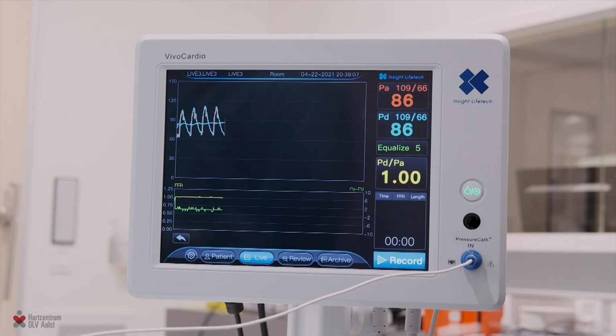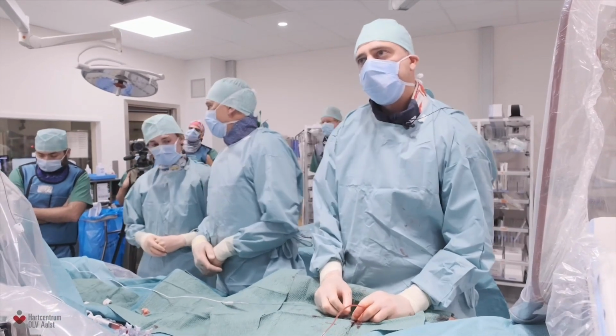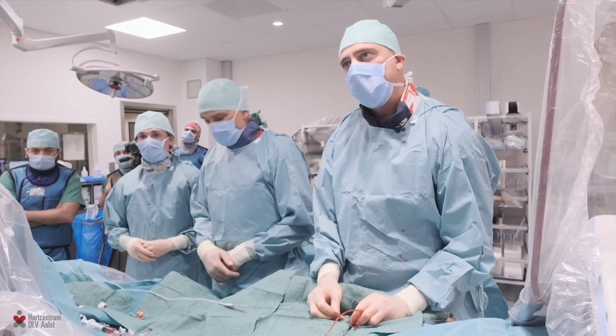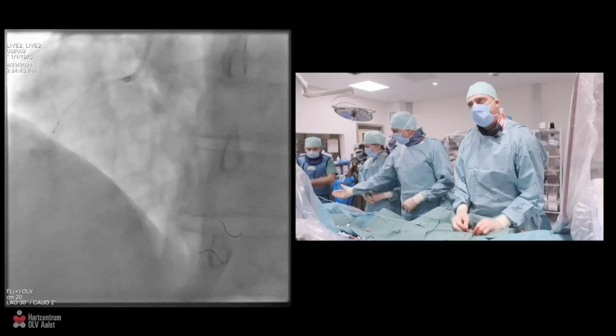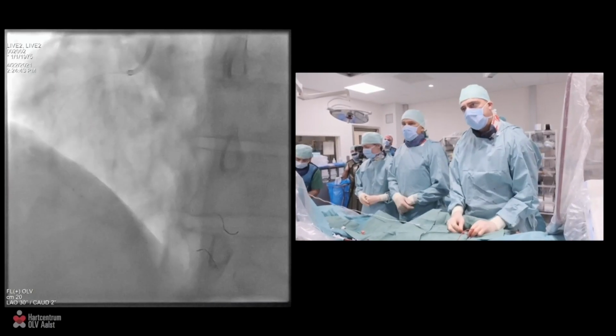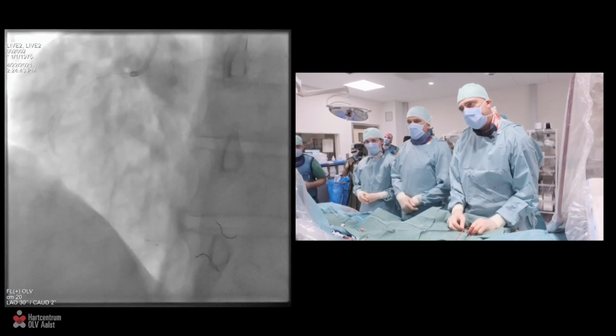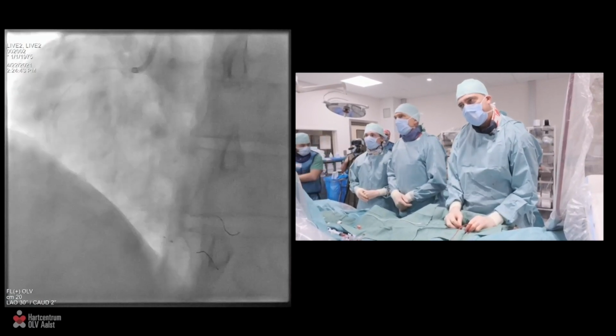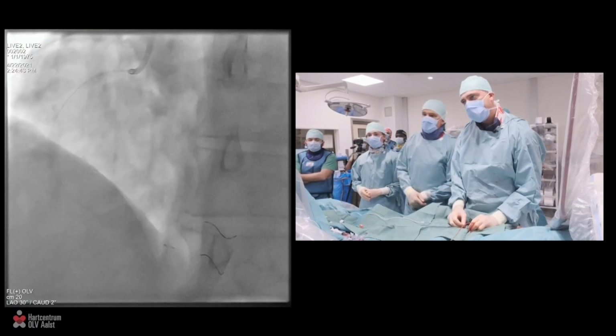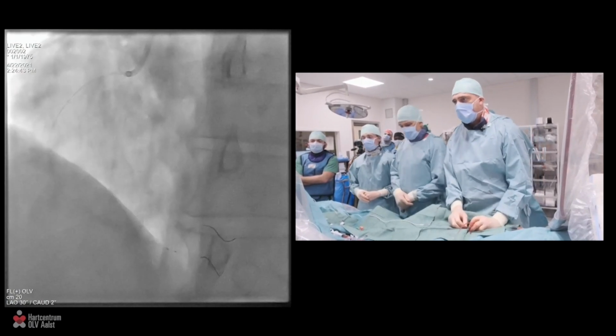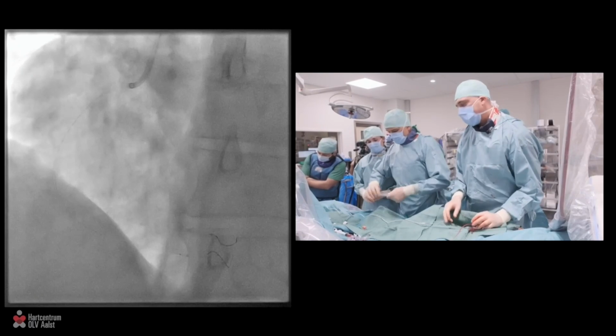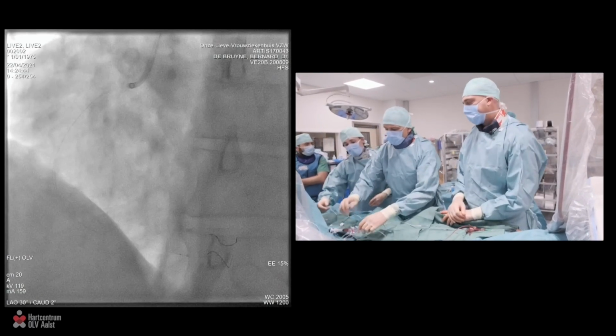Perfect. So after the equalization and confirming a PD/PA value of 1.0, we push the microcatheter down. The pressure sensor is almost at the tip of the catheter. You see the markers in the distal posterior branch, and now we're ready for a measurement.